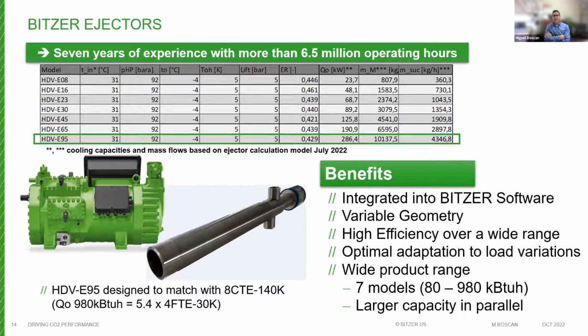Perhaps the biggest benefit of using the BITZER ejector is that it is going to be fully integrated into our BITZER Analog software. This will greatly simplify the selection of the compressors and ejectors, and the manipulation of compressors and ejectors, to really dial into the best option for the end user, the final customer. That release software should be in one of the next couple of revisions of our software. There was a software release today that did not include it, but it should be coming up in the very near future.